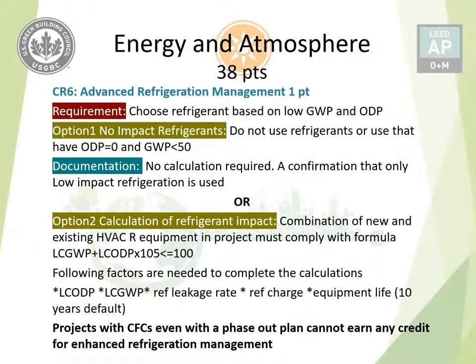Option number two is calculation of the impact of a certain refrigerant that you are using on your site or in your project. The combination of new and existing HVAC equipment in the project must comply with the formula: life cycle global warming potential plus life cycle ozone depletion potential times 105 should be less than or equal to 100.